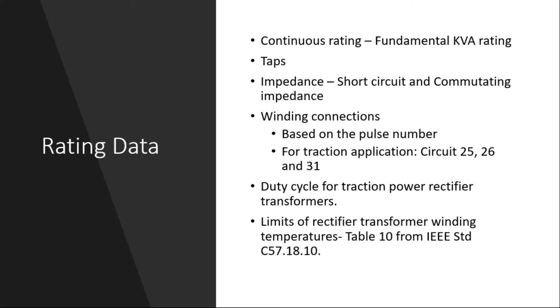So the rating data requirement for these special applications involves something called fundamental kVA rating. So what is fundamental kVA? Fundamental kVA rating is just the RMS value of the fundamental current, and this is used for the commercial loss guarantees. And the RMS kVA, which is used for loss and other calculations, is calculated from the RMS value plus the associated harmonic currents. So what happens when the transformer is designed, the base value is increased to provide cooling.